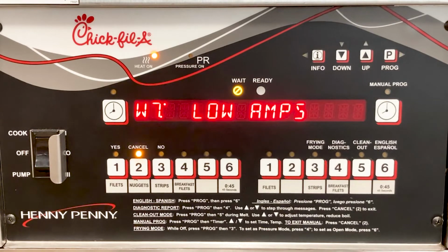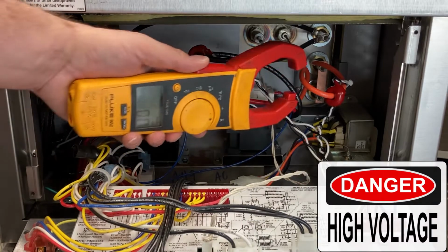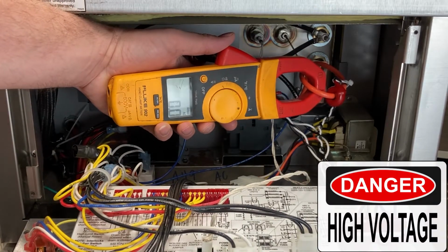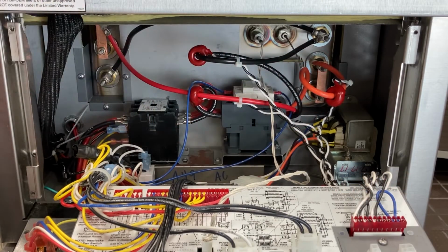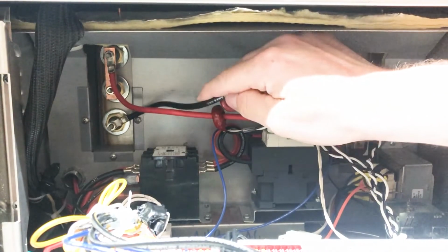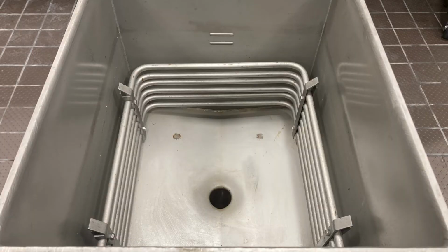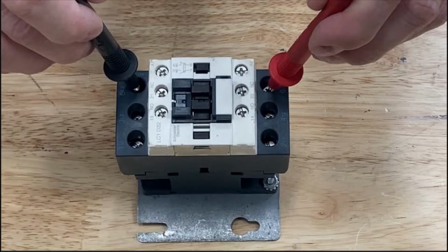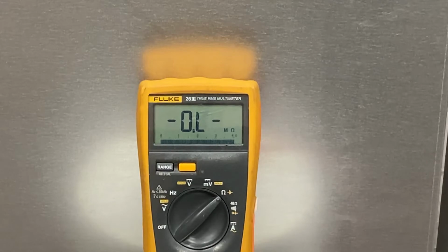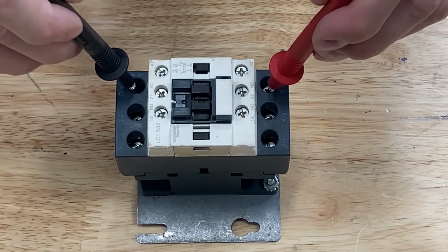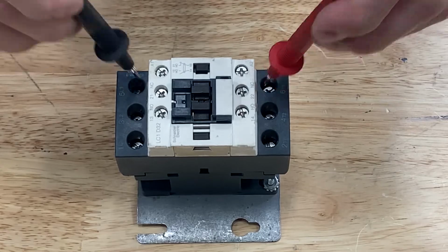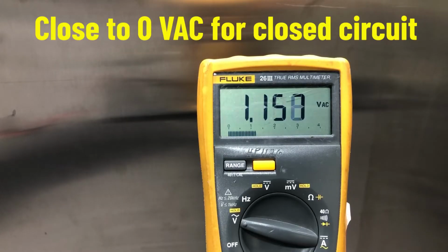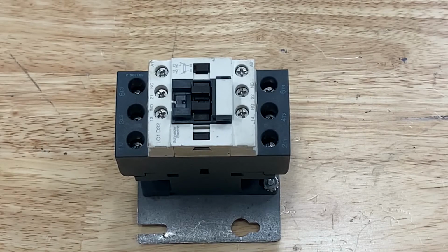For a scenario where the amp sensor reading on the control gives a reading of 0 or a reading lower than the other two, and that matches your amp draw reading that you took with your multimeter, then this could indicate a burnt wire, loose or burnt connection, bad element, or possibly one leg of the contactor not closing. To check this, visually check for burnt wires or loose connections. Then take a voltage check across all three legs of the contactor, ensuring it is working properly.